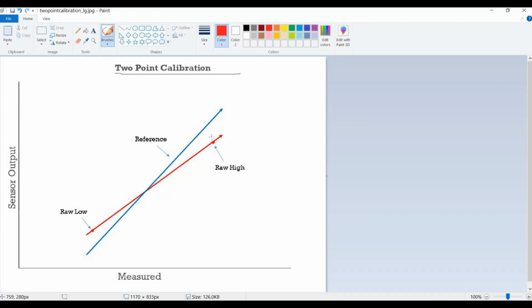So we will have 2 points to calibrate because if you remember in the first part where we have a single point, mostly the raw data will be adjusted in a linear manner, or rather in the same offset. For example, this is our reference in the blue. So previously, let's say this is uncalibrated data, all of it will go down or go up by a constant factor. But we noticed that at the low end and the high end, the accuracy was out, and in the middle range, the accuracy was acceptable. So in this case, we can use a 1-point calibration. Otherwise, we need to go to the 2 points.